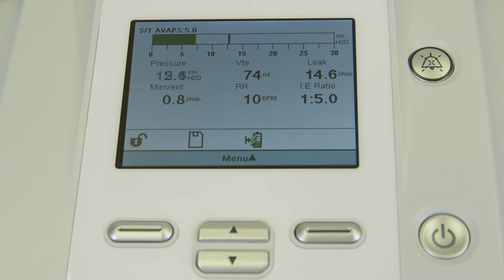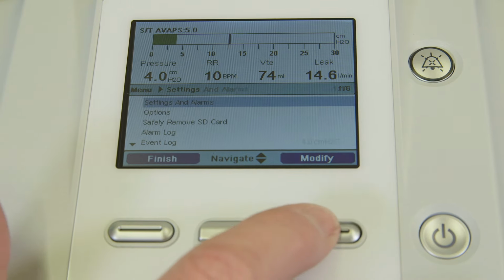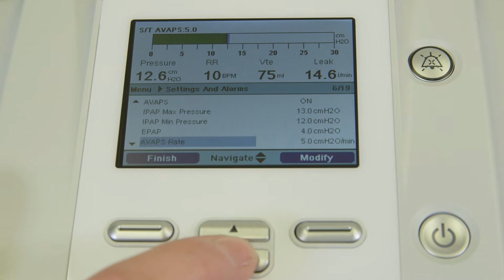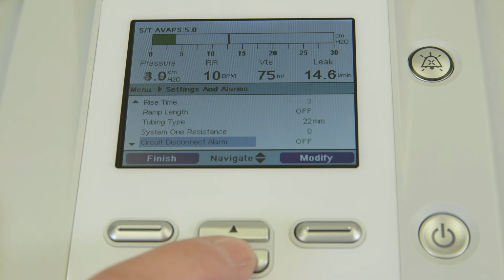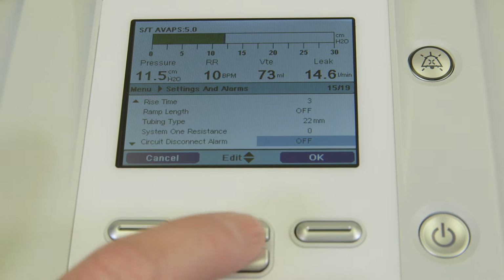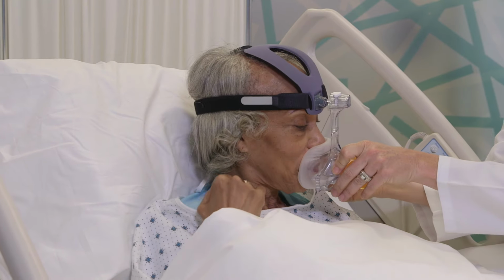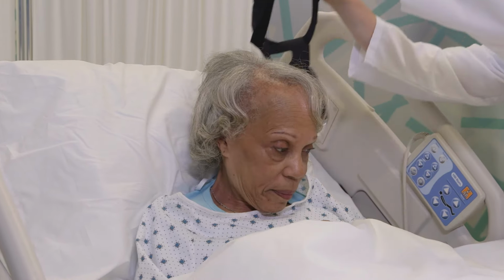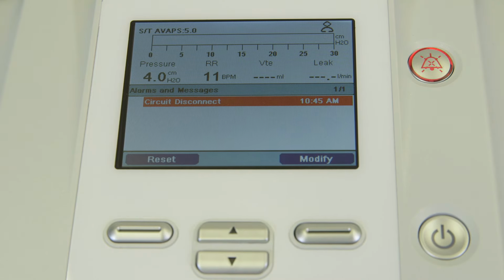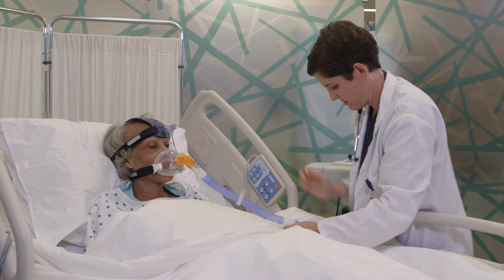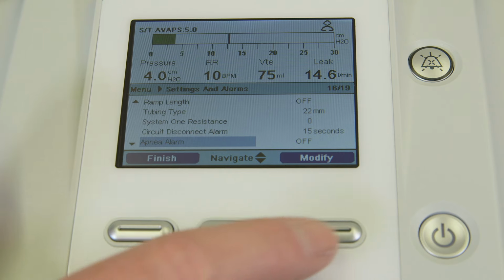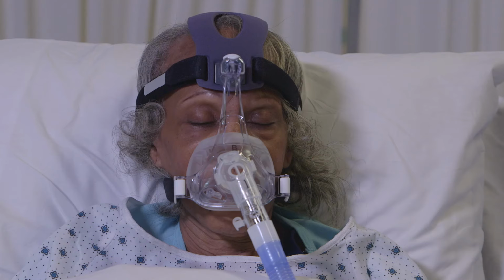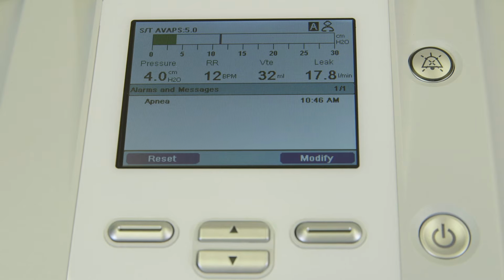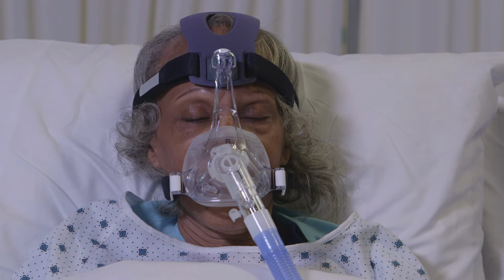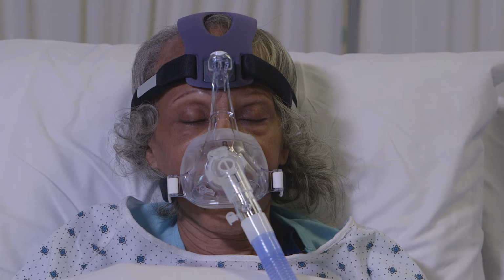The V30 has several alarm options located in the Settings and Alarms menu. Using the down arrow to navigate, you first come to the Circuit Disconnect alarm. When a large continuous air leak is detected in the circuit, such as the patient's mask being removed during therapy, this high-priority audible alarm will sound. The audible alarm will terminate once the leak is corrected. Next is the apnea alarm. This high-priority alarm occurs when the patient has not triggered a breath within the time specified in the alarm setting. The alarm will automatically terminate when 2 consecutive patient breaths are detected that meet the apnea alarm time setting.